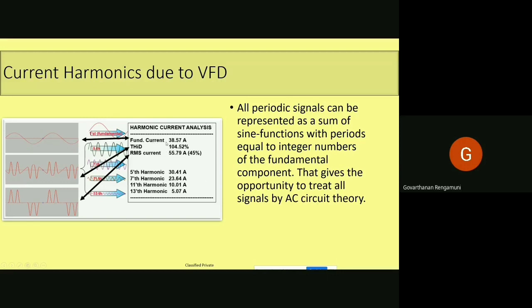You can see the fundamental current is 38.57 ampere, the total harmonic distortion is 104.52, and the RMS current is 55.79 ampere. So you can see you have a lot of harmonics present here. If I decompose into harmonics, you can see the fifth harmonic is 30 ampere, the seventh harmonic is 23, the 11th is 10, and the 13th is 5.07.